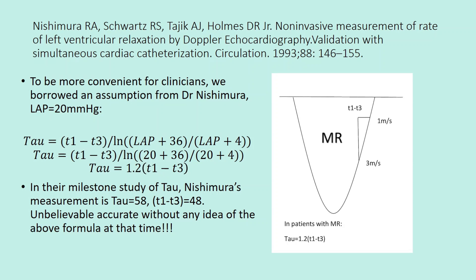In Nishimura's milestone study of tau, his measurement gave tau equals 58 milliseconds, while T1 minus T3 equals 48 milliseconds — unbelievably accurate. Remarkably, nobody knew the above formula yet at that time.